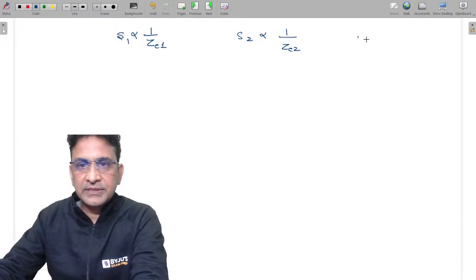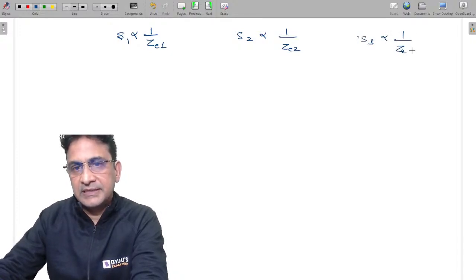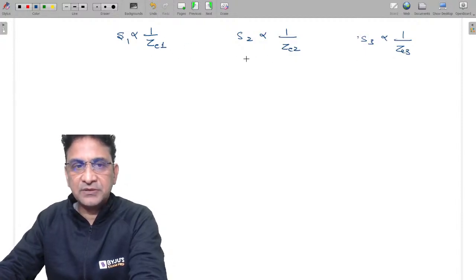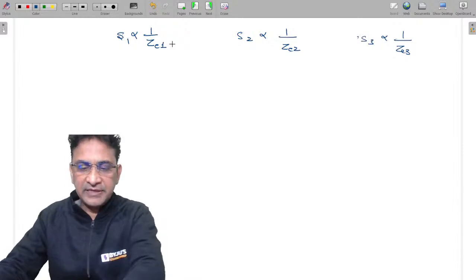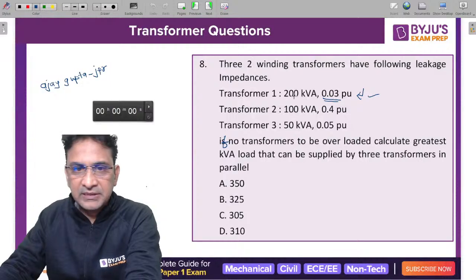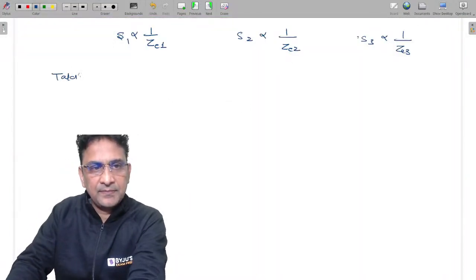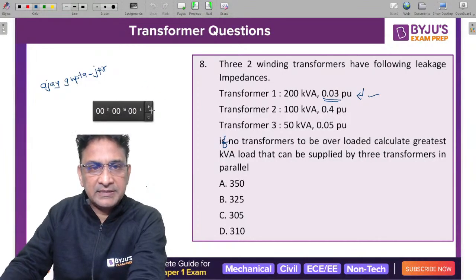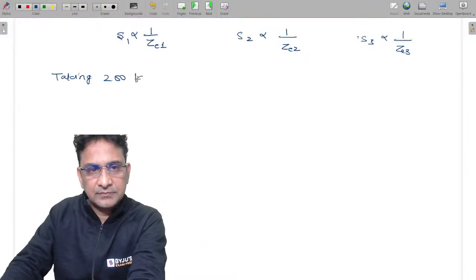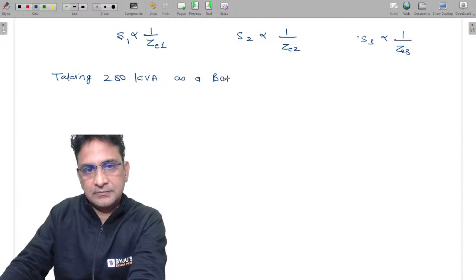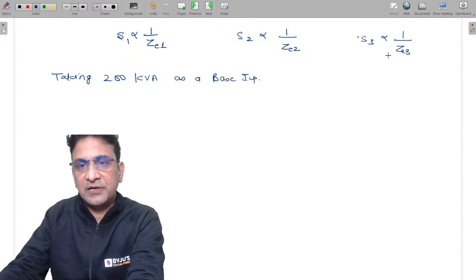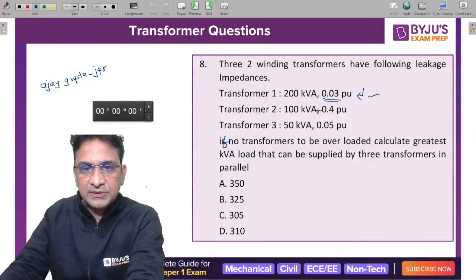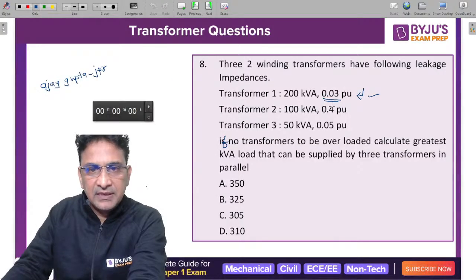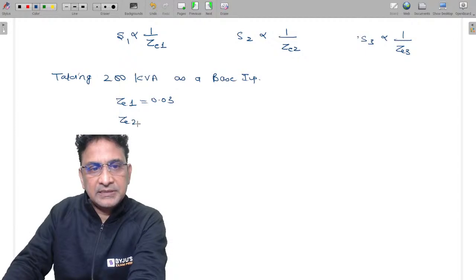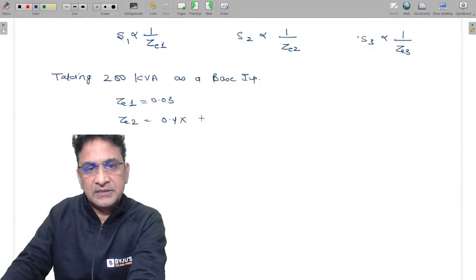Okay, so load sharing by transformer 3 is inversely proportional to its leakage impedance. In this formula, either we have to use the actual value of leakage impedance or convert all the leakage impedances into the same base. So I am converting all impedances into the same base. I am taking 200 kVA as the base, because either you use the actual value of impedance or convert into the same base value. So the leakage impedance of transformer 1 will remain the same, 0.03. But the leakage impedance of transformer 2 becomes 0.4. I am converting this into the 200 kVA base. Its own base was 100 kVA. So it becomes 0.8.